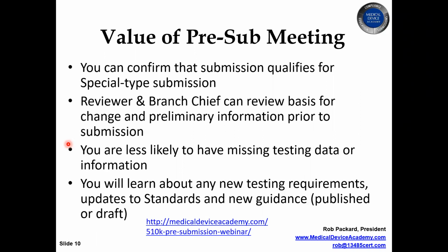that you have. So even though they only have 30 days for the review of your submission, if they've already seen it as part of a pre-sub, they may be more familiar with it and things might go a little faster for them, so they're more likely to be able to complete it within that 30 days. They also can see what areas are going to be a problem and give you a little attention to, hey, this is the part of the submission that's most important for us to have very clear, and this is what we're looking for in the special submission.